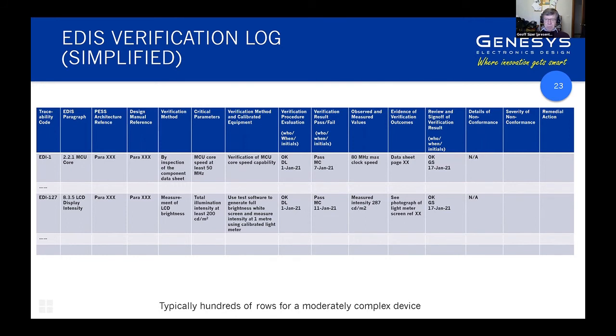Now, we'll refer to that very important clause in 60601-1 that says if you comply with an objective requirement that's explicitly stated in 60601-1, that indicates that you have taken sufficient risk mitigation process for that risk.